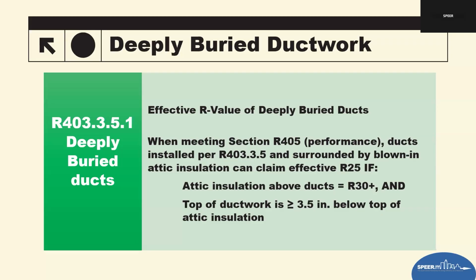In addition, the top of the ductwork must be buried at least 3.5 inches below the top of the insulation level. These two conditions together create a thermal buffering effect that allows the code to treat buried ducts as having a higher effective insulation. This was added in the 2024. I like it. It makes sense if people are going above and beyond and trying to get more insulation value for ductwork by burying it deeply in insulation. This is a great way to do it. As I said earlier, we may not see this happening in Texas, but someone may be building a high-performance home and trying different things to see if this works. So this is a meaningful new credit for builders in Texas who are already burying ducts. I don't know of anybody that is. It rewards good insulation depth, proper installation, and can actually help meet better ERI targets if that's what you're using to move through the code.